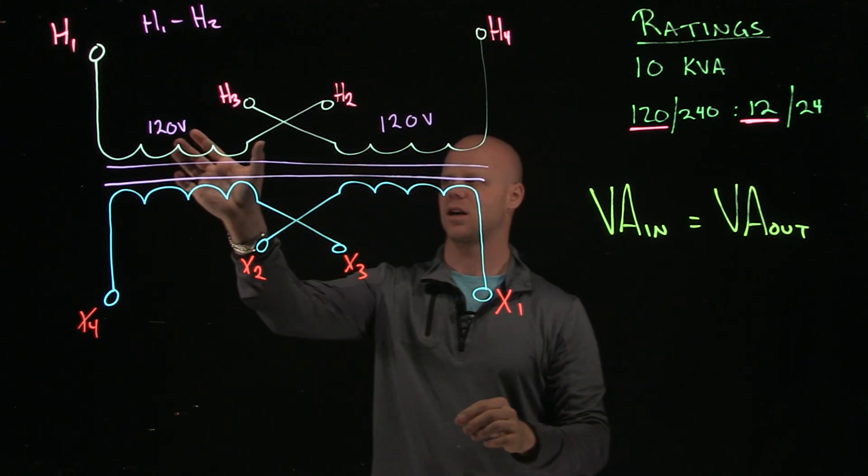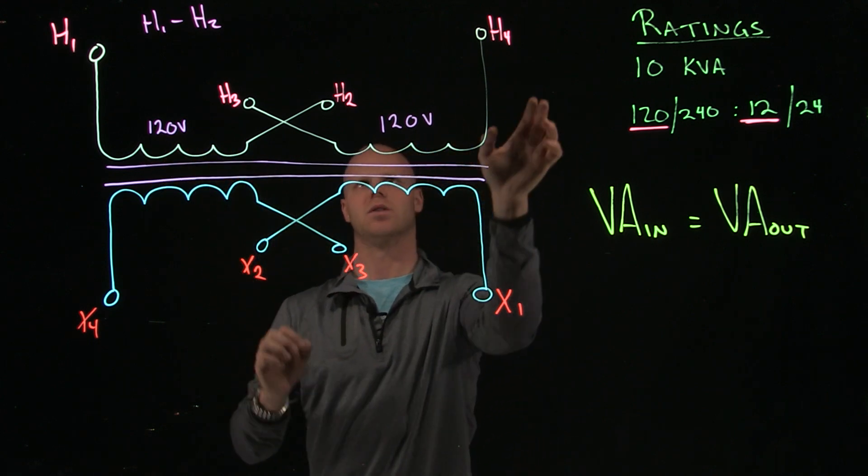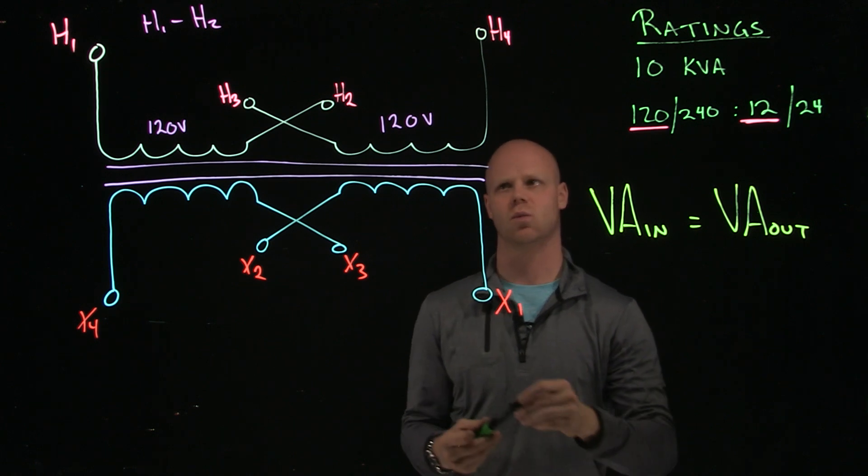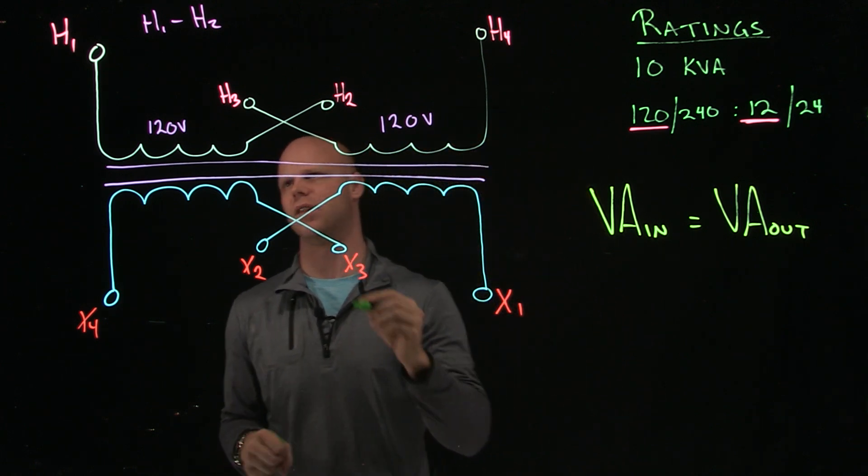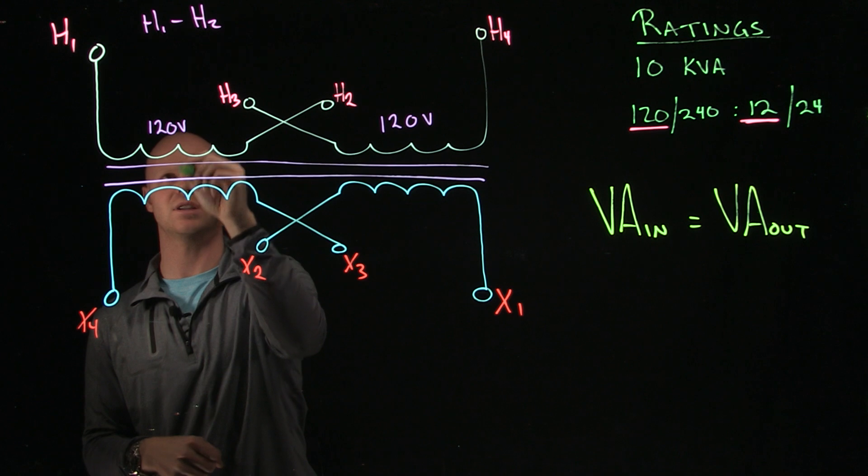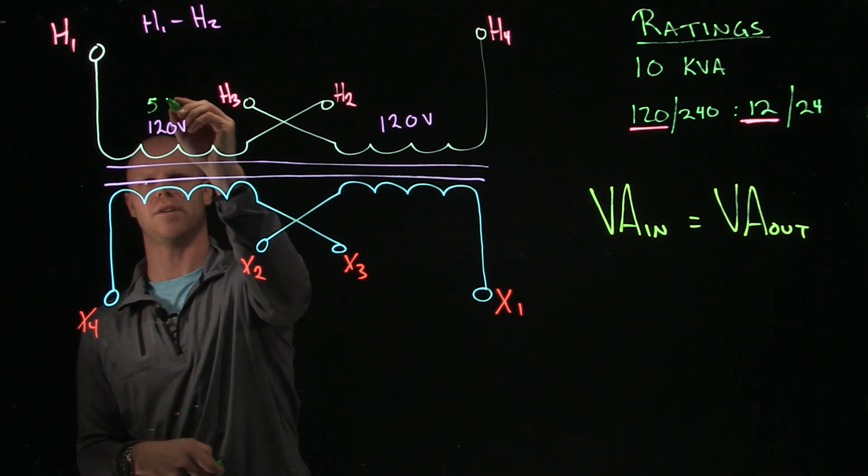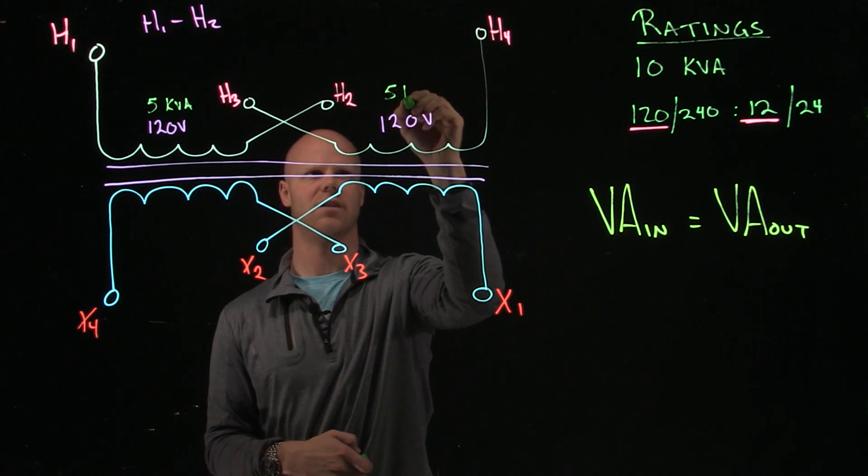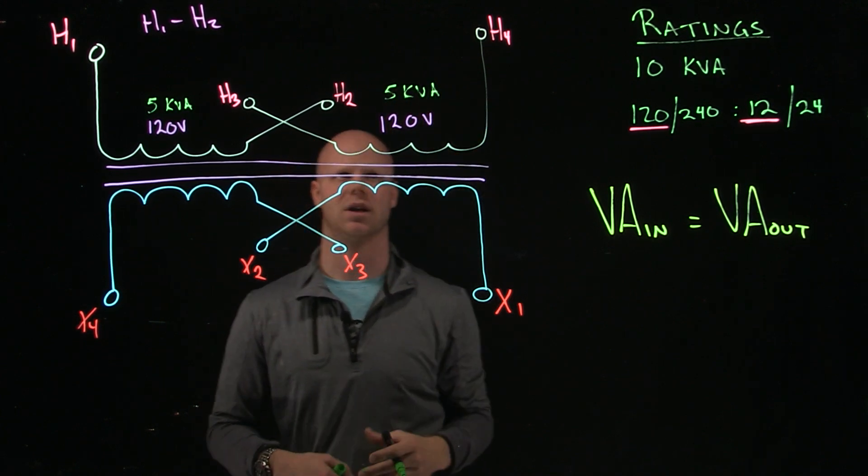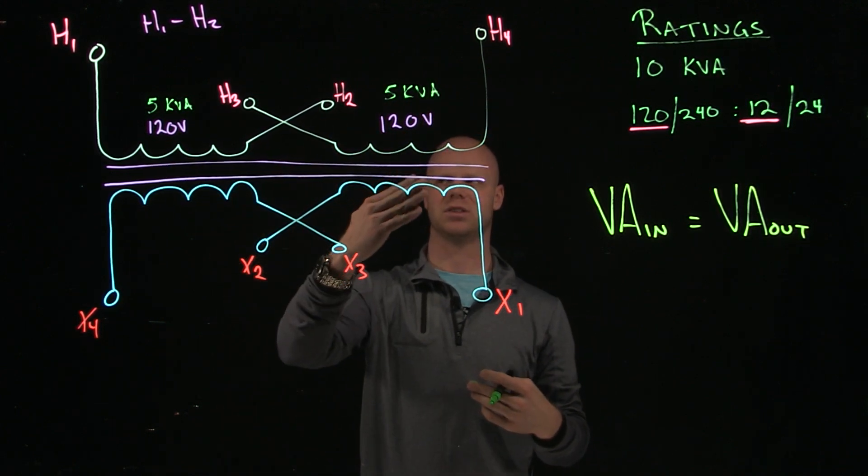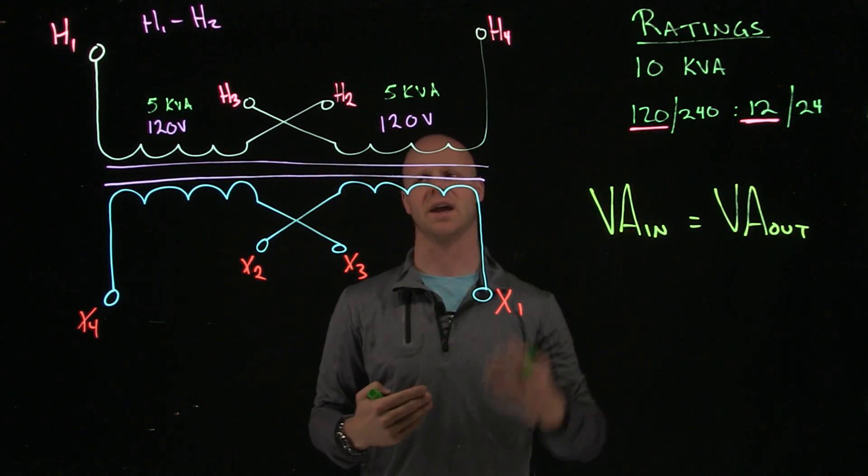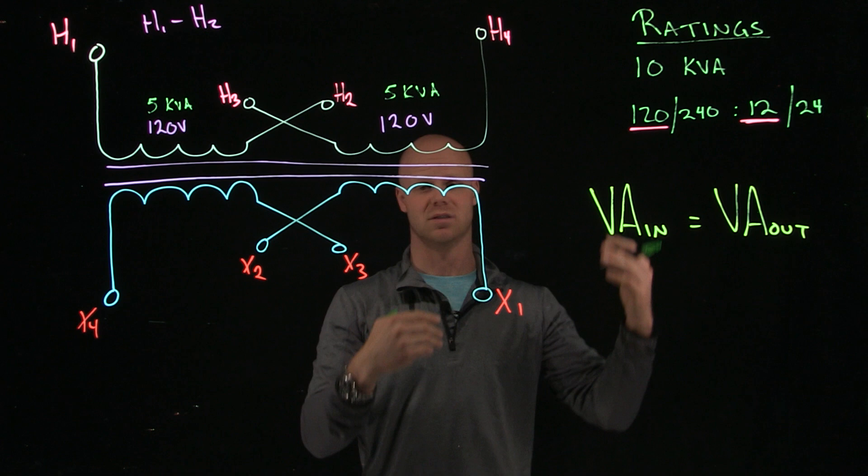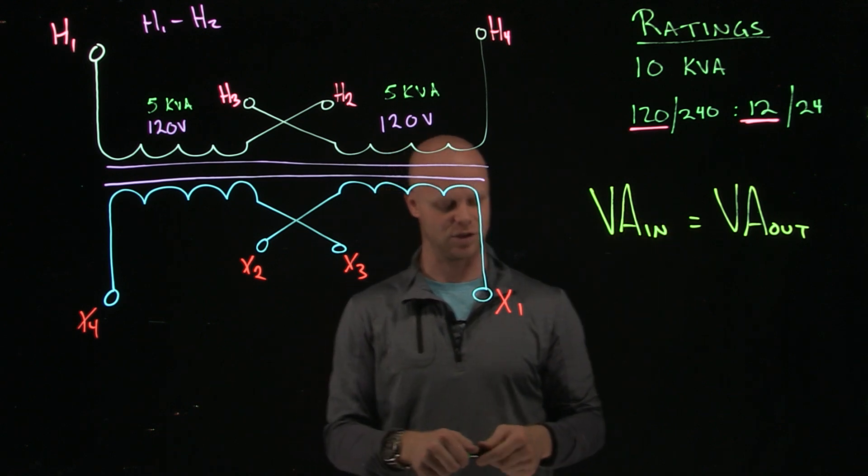So if that has 120 volts, this has 120 volts. My entire H side is good for 10 kVA, that means each winding will share that VA. So just this one winding will have a 5 kVA rating, and this will be a 5 kVA rating for this winding. Now it doesn't matter. If I wire them in series, 5 plus 5 is still 10. If I wire them in parallel, 5 kVA plus 5 kVA is still 10 kVA. Everything is still true.